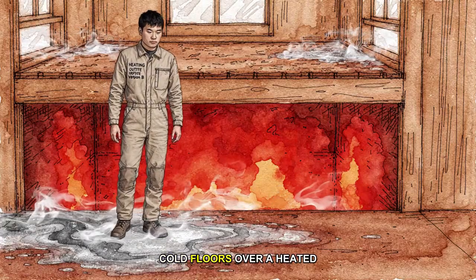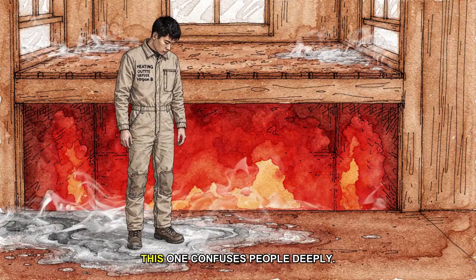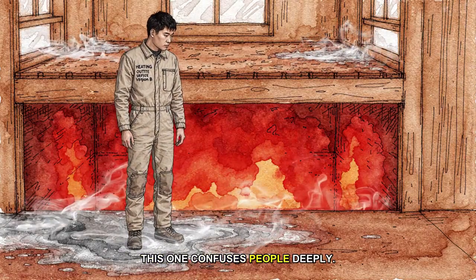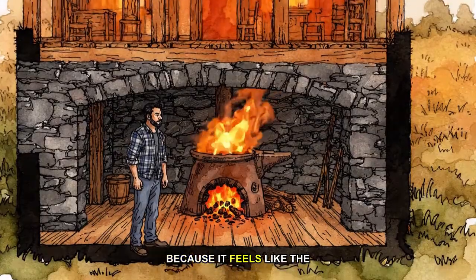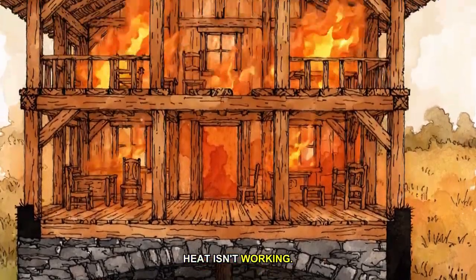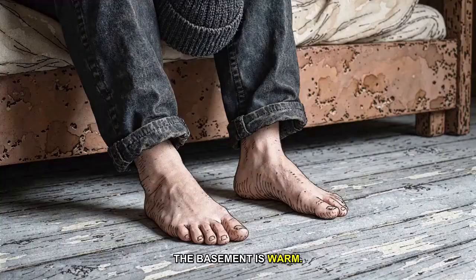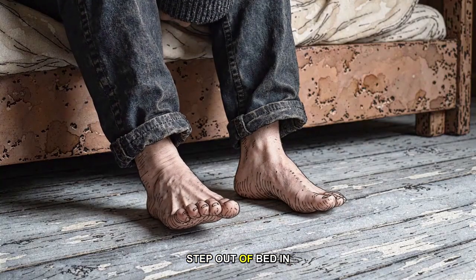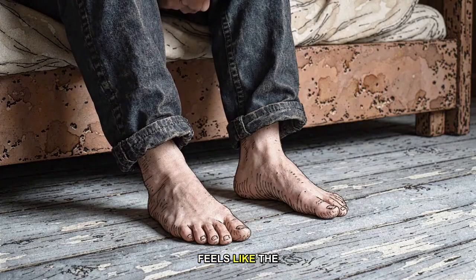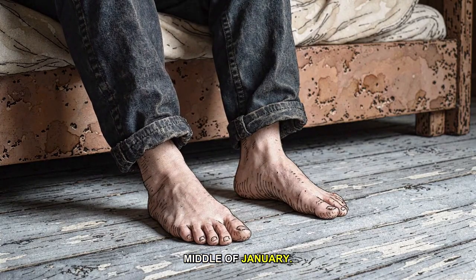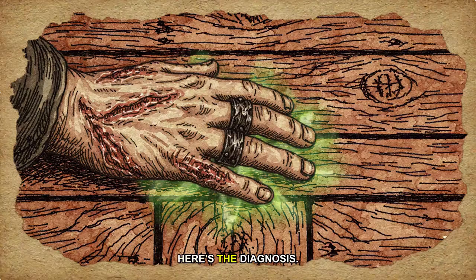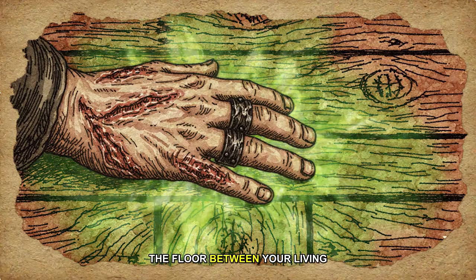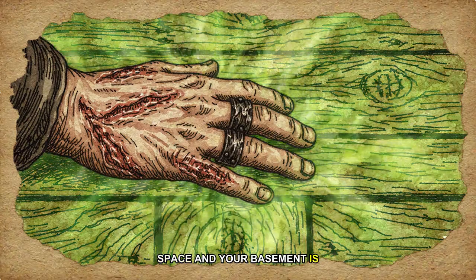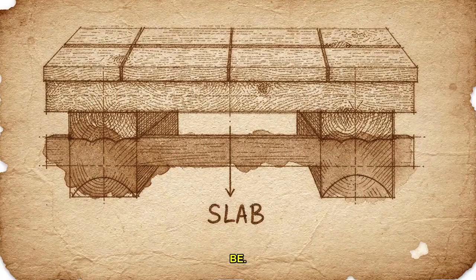Cold floors over a heated basement. This one confuses people deeply because it feels like the heat isn't working. The basement is warm. The furnace is running, but step out of bed in the morning and the floor feels like the middle of January. Here's the diagnosis. The floor between your living space and your basement is where the thermal boundary should be.